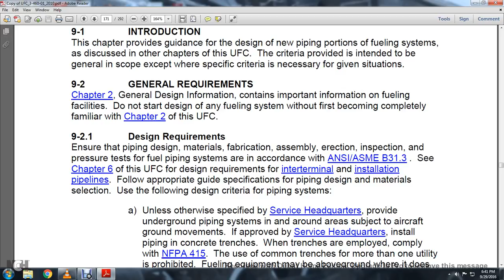Provide underground piping in and around the area subject to aircraft ground movements, if approved with the service headquarters. Install the piping in concrete trenches. When trenches are employed to comply with NFPA 415, the use of common trenches for more than one utility is prohibited. The fueling equipment may be above ground where it does not interfere with the aircraft or surface vehicle movements.